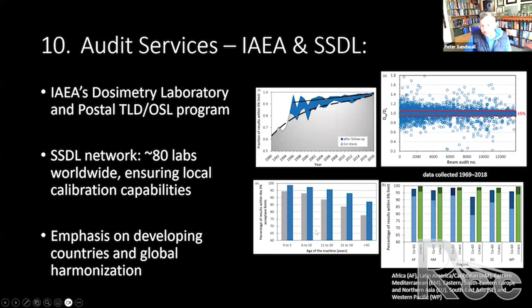These are some other things that they learned. Here, the age of the machine matters. The blue is cobalt. The gray is a linear accelerator. You see that the older the machine, the more variability there is in the calibration, with linear accelerators being less reliable with time than cobalt units.